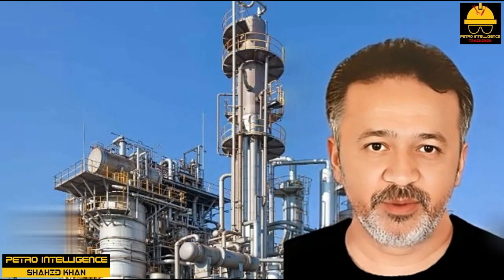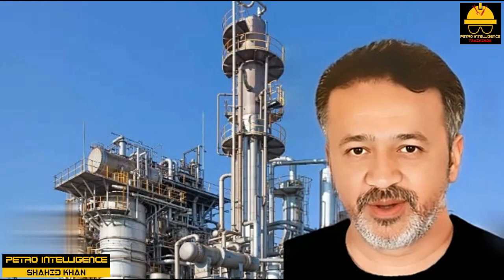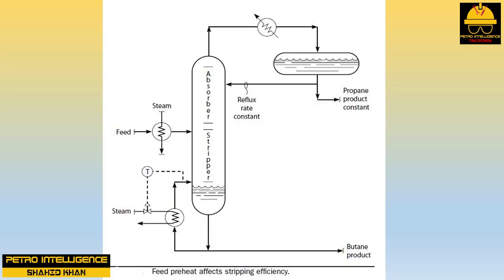Effect of feed preheat: up to this point we have suggested that the weight flow of vapor up the tower is a function of the reboiler duty only, but this cannot be completely true. Looking at this picture, increasing the heat duty on the feed preheater will reduce the reboiler duty. Assuming both the reflux rate and overhead product rate are constant, the total heat flow into the tower is constant — meaning the sum of the reboiler duty plus the feed preheater duty is constant. If steam flow to the feed preheater is increased, the reboiler duty will fall.